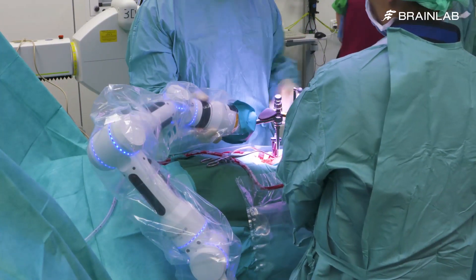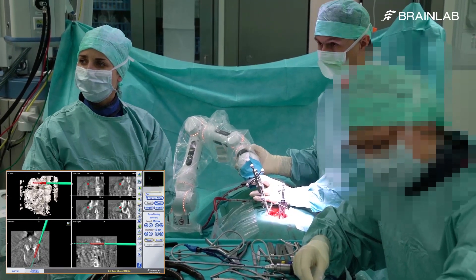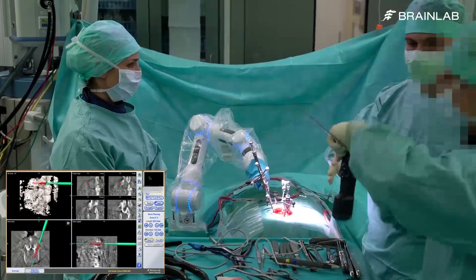The SPI navigation software helps the surgeon align the drill guide to the trajectory. When the system is aligned with a trajectory, the grip sensors lock Cirq securely in place. A snap-on depth control guide can be attached to prevent the drill bit from exceeding the trajectory target.